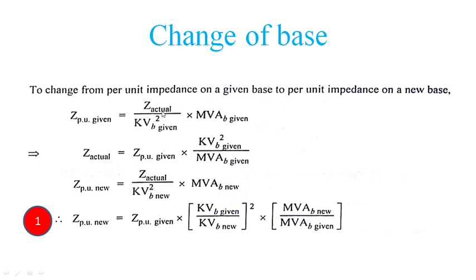Next, from this, find the expression for Z actual. So Z actual is equal to Z per unit given into kVB square given divided by MVAB given. So it's the expression for the given per unit impedance. Similarly, you can write the equation for the new per unit impedance value, that is Z per unit new. Here the only change is that it is a new value, so you can replace the subscript given with new.